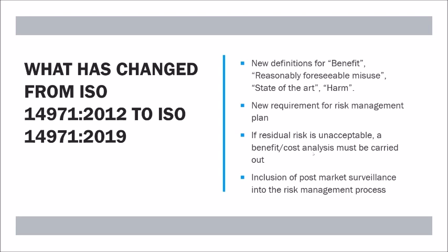Now, state of the art, as a concept, is basically looking at the wider market and seeing what the accepted technology, the accepted risk, the accepted use is in general literature around. So it's doing that due diligence of looking at other similar products on the market and ensuring that your product is in the same sort of state as those other examples that are already in the market. There's also a new definition for harm. I'm not going to go into specific definitions apart from state of the art, just because we're going to focus on risk acceptability criteria in this video.